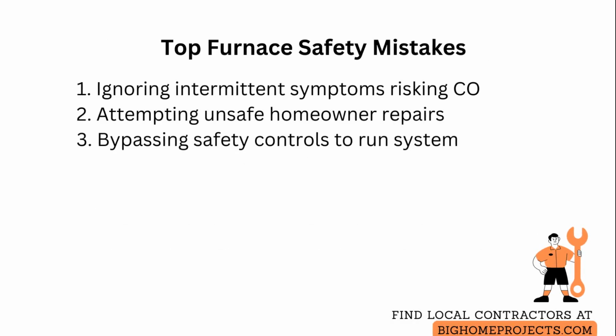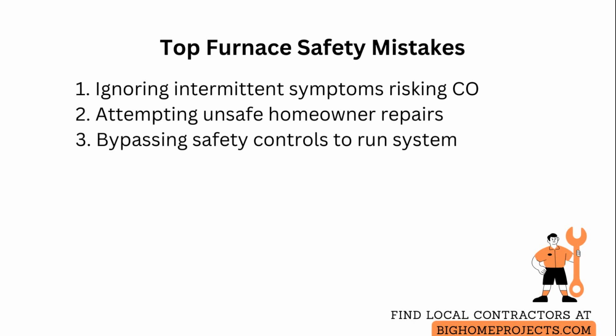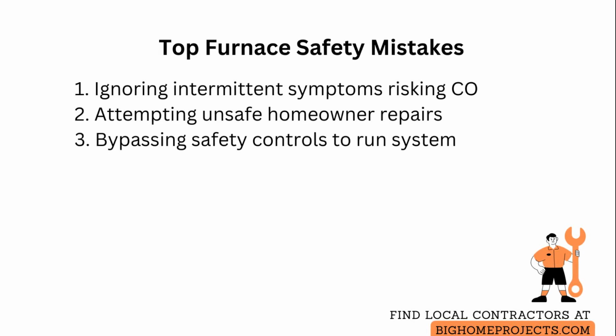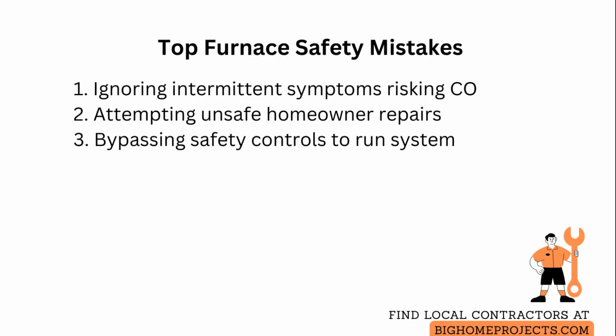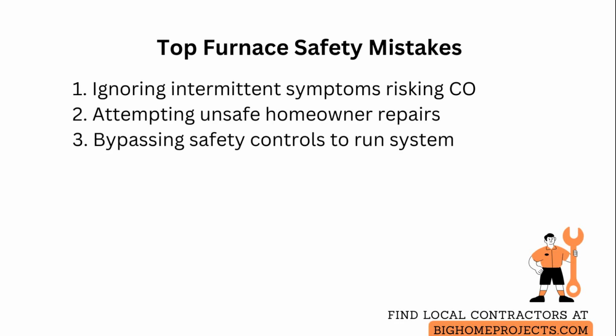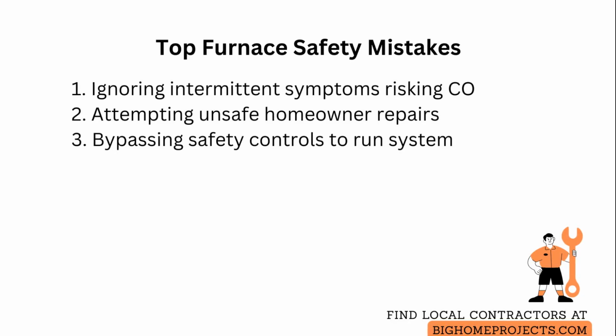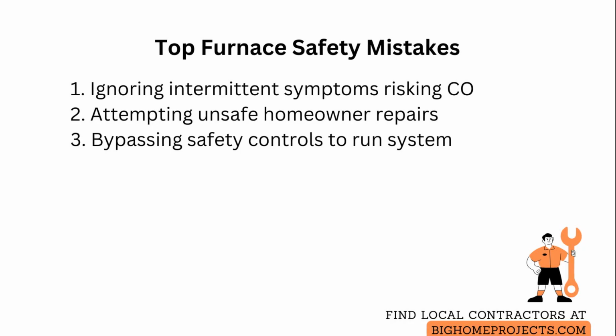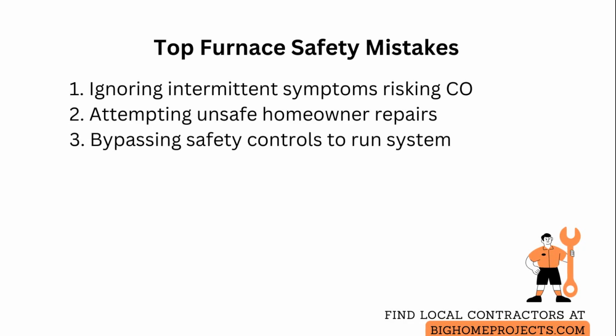Common mistakes include ignoring intermittent symptoms because the furnace still produces heat, which risks ongoing carbon monoxide exposure and delayed detection. The fix is immediate shutdown and testing with a detector and professional inspection. Another error is attempting homeowner repairs such as welding or using high-temperature sealants on the exchanger, which rarely restore structural integrity and can create dangerous hidden failures. The correct action is replacement with the proper part installed and tested by a trained technician.